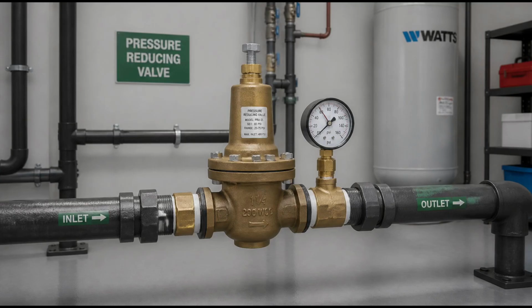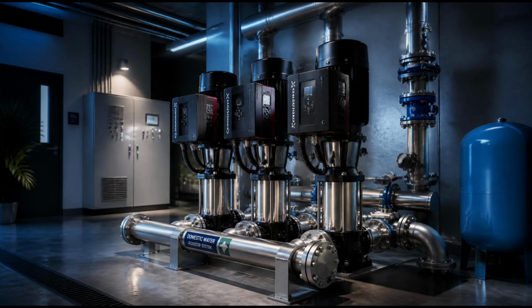For most commercial buildings, the target pressure after regulation falls somewhere between 40 and 80 pounds per square inch. At the lower end of that range, there is enough pressure to serve fixtures on higher floors and to maintain good flow throughout the system. At the upper end, fixtures still operate comfortably without being subjected to more force than they need. The specific set point for a given building depends on its size, the height of the structure, and the demands of its particular fixtures and equipment.